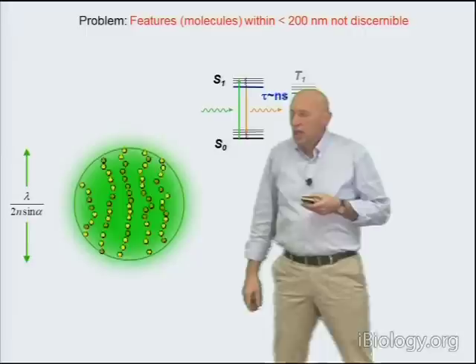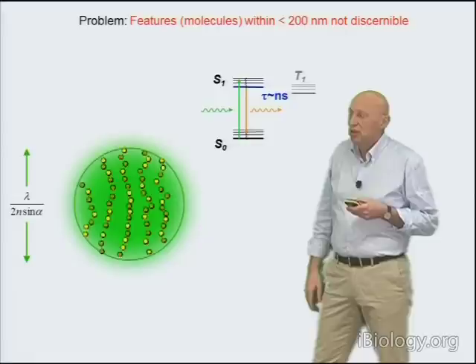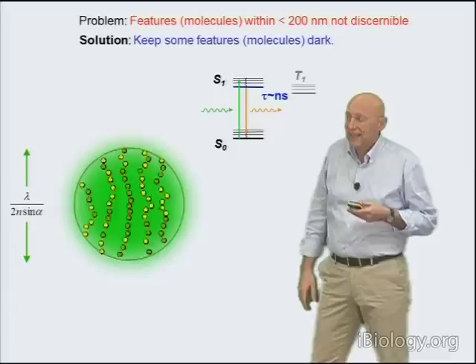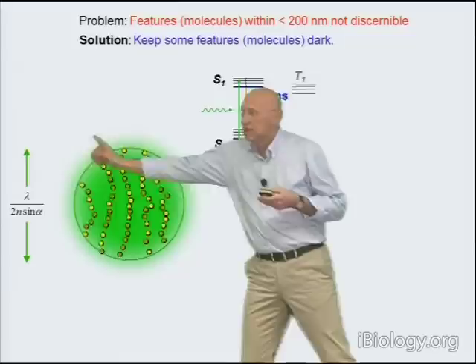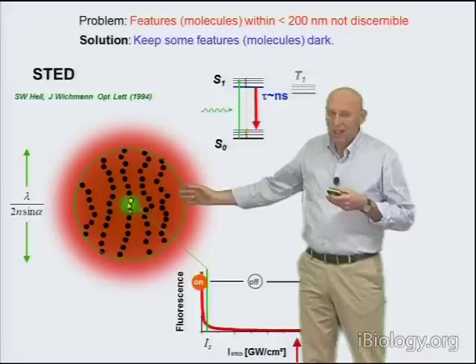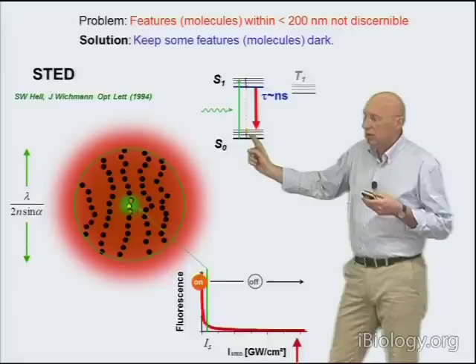If the problem really is that all the features are flooded at the same time with excitation light and hence give off light at the same time, a solution is to make sure that not all the features inevitably flooded with excitation light are in the end capable of emitting. This is exactly what we do in a STED microscope. In the STED microscope, we not only use a beam for exciting molecules focused into this 200-nanometer range, but we also use a beam of light typically shaped as a doughnut, whose role is to keep the molecules dark — to turn them off.